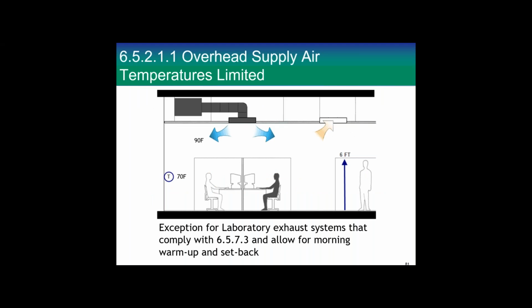Overhead supply air temperature limited. So this is what I was talking about just a minute ago. For 90.1, if you were heating to 70, which would be high, then you could go to 90. That's a 20 degree difference between the thermostat and the supply. Now, why that is: air flowing from a ceiling diffuser likes to hug the ceiling. This air is hotter than the air of the room, so it likes to hug the ceiling, so it may not get down there and heat the room when the return is at the same level. If you move this return within 6 feet of the floor, then the requirement's off.